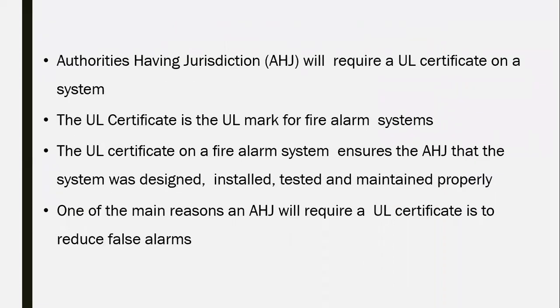What about the FM? Okay. Before we go to this one, the authority having jurisdiction, AHJ, which will require the UL certificate. This authority here in Qatar is the QCDD, Qatar Civil Defense. So they might require it or not, depending on the authority, but most of the authorities and the civil defense governments require UL and FM certified. It has to be for the fire alarm, for the life safety devices, starting from the fire alarm, exit signs, and the pump itself.